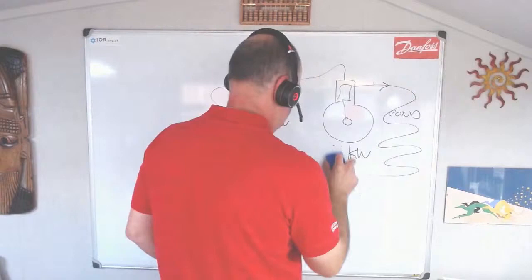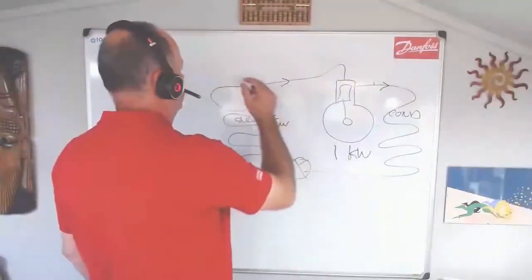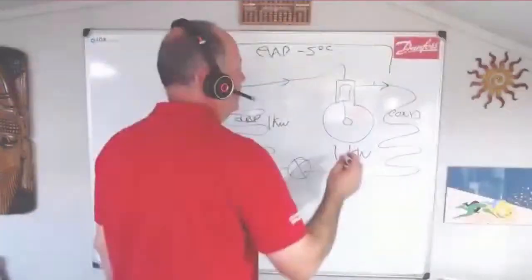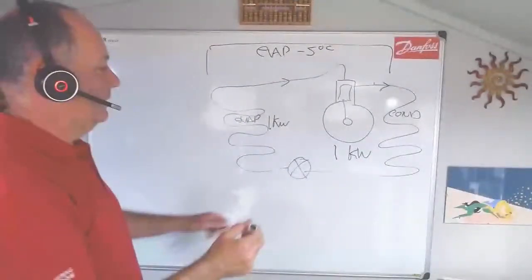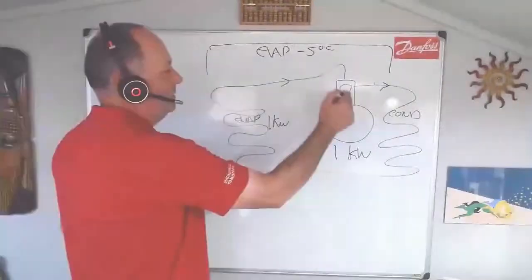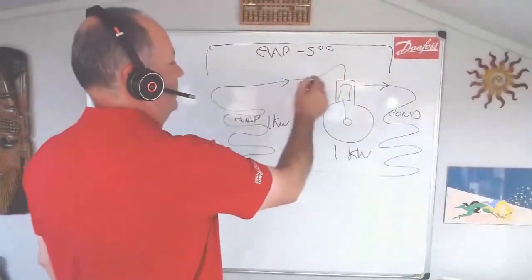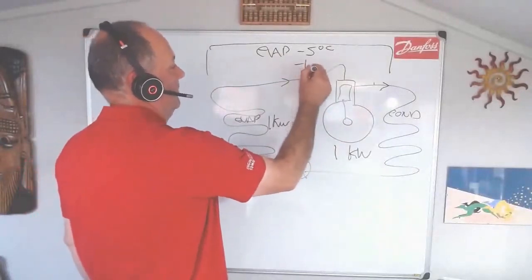So we've got one kilowatt, one kilowatt, and that system is designed to evaporate at, let's say, minus five. All of a sudden, if you've got a bigger compressor, instead of evaporating at minus five, because that's sucking more on the suction, we might evaporate at minus ten.